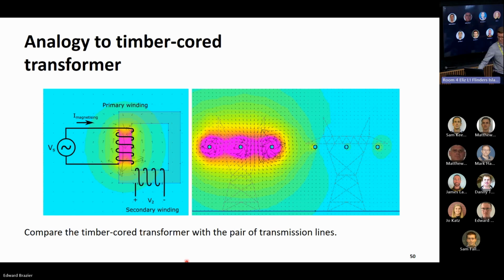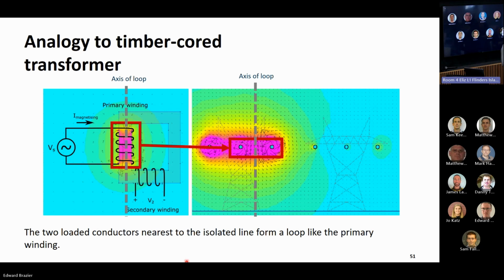So we can look at the primary winding of our timber-cored transformer. It's oriented around the vertical axis. If we choose two of the three conductors on the in-service transmission line, it's the same thing, oriented around the vertical axis. The main difference is just on the transformer, you've got conductors looped around many times, whereas on the transmission line, they're not looped, but they extend far into the distance. So in both cases, the conductors are long, and because they're long, they can produce a lot of magnetic flux.